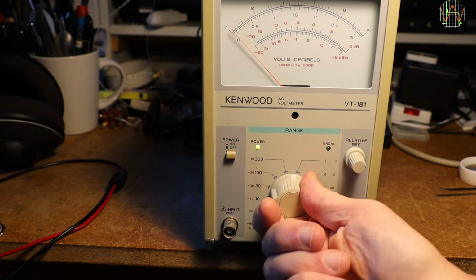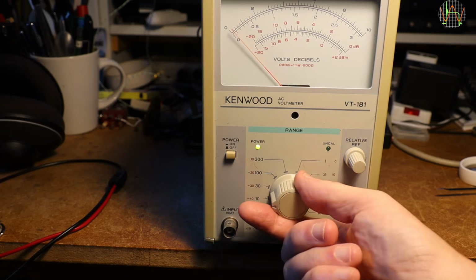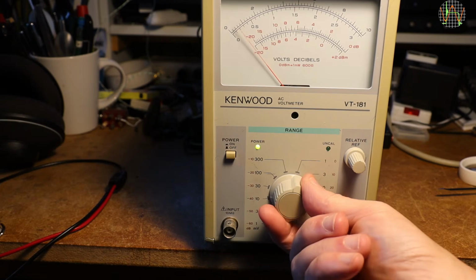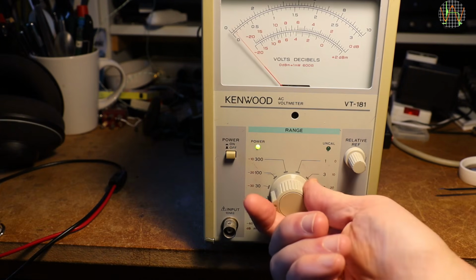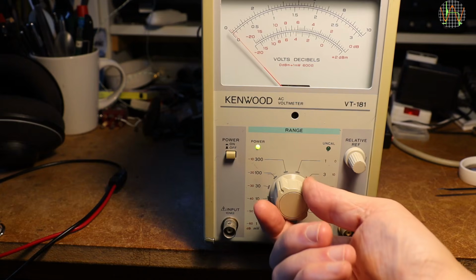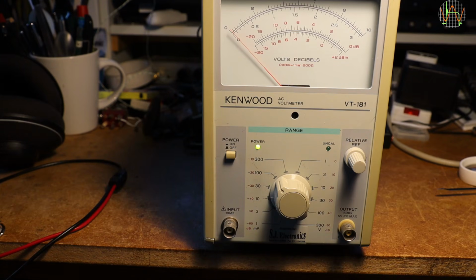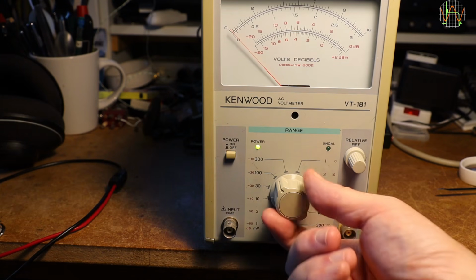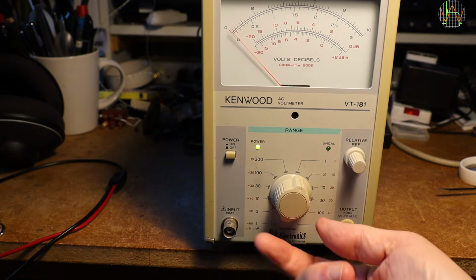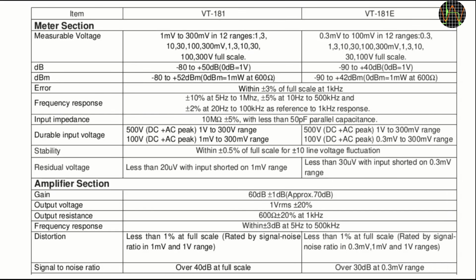With that fixed, the zero offset is even more pronounced. Okay, I think the main reason was that it was set to the most sensitive position and picked up noise. Changing to 100 mV full scale, and the offset is nearly gone. There are actually two models of the VT-181: the standard one that I have and the VT-181E.